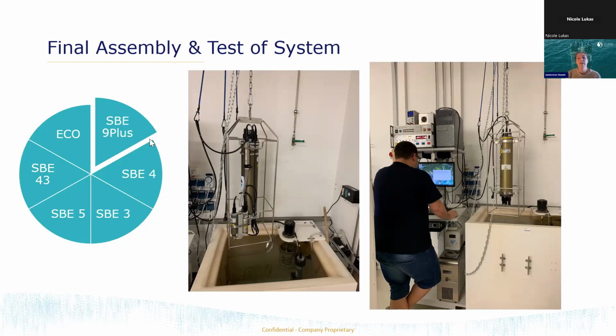This is essentially a dunk tank, salt water that we keep at 2 degrees C. What we're checking for is that as we take an instrument or system from room temperature down to how it's going to be used when deployed overboard, all of those individual components are responding appropriately and playing nice with each other.